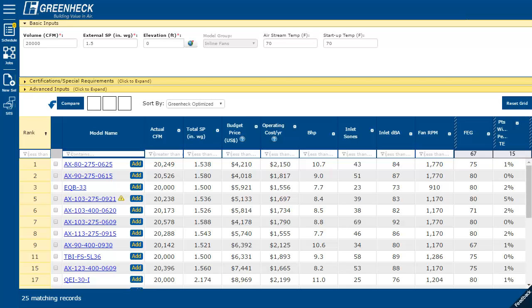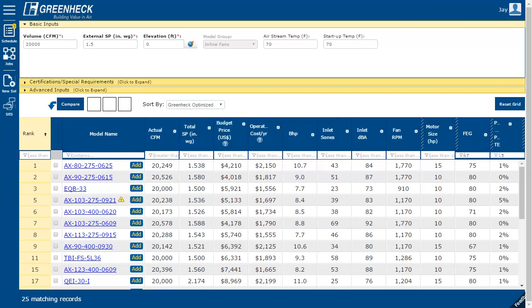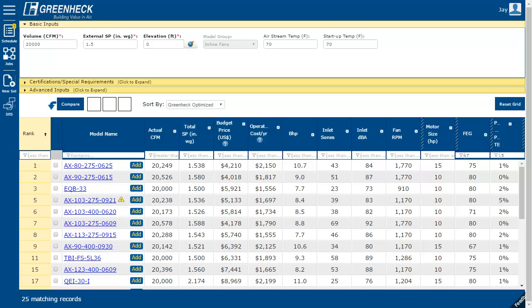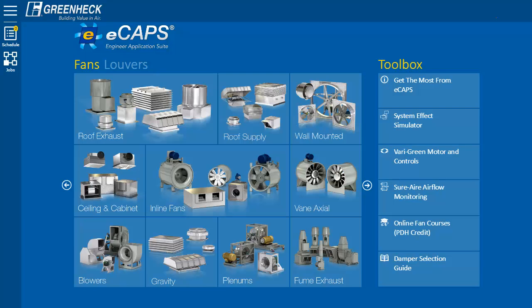Notice the grid columns were added. You can type in your local code requirements, such as a minimum of 67 FEG and 15 points within peak. Now your selections all have a minimum of 67 FEG and are within 15 points of peak. You can also add the Motor Size column to check if this selection is exempt because of the 5 horsepower minimum. This was a quick demonstration of how to access the fan efficiency information in E-CAPS. Thanks for learning what is happening with fan efficiencies at Greenheck.